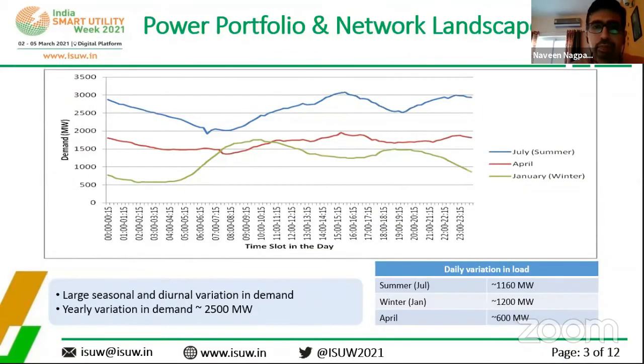This is a load curve I want to highlight. In Delhi we have three different seasons in terms of the power load curve. The blue curve represents a peak summer day, where demand goes as high as over 3000 megawatts, and on the same day the lowest demand touches below 2000 megawatts — a diurnal variation of almost 1200 megawatts. Likewise in winters, the green curve also shows a daily variation of around 1200 megawatts, and the yearly variation is more than 2000 megawatts, touching around 2500 megawatts.